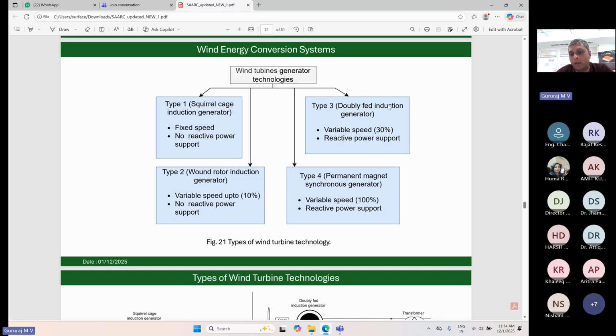Then type 4, where we go for permanent magnet synchronous machines. The complete wind speed variation is allowed here, but you may need full rated converters to convert from AC to DC and DC to AC. One good advantage of the type 4 generator is that any dynamics seen on the grid side are not reflected on the machine side. Whereas in the case of the type 3 generator, if there is a fault on the grid side, that is reflected on the stator side. So that may lead to some research challenges, which I'm going to discuss in due course of the presentation.